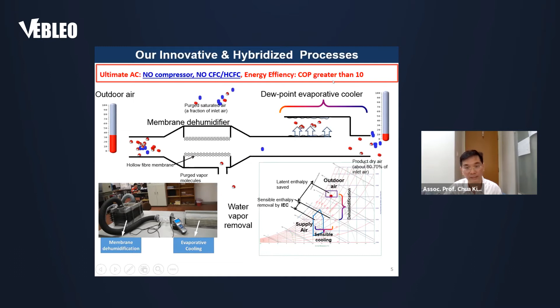So one stage of this system, the dry and wet channel, will be able to drop the temperature of the air by about 3 to 4 degrees. So if you desire maybe about 10 degrees of temperature drop from your air, then you need to repeat this process 3 times. In other words, the air that is coming out from this entire system is both cool and dry, similar to what you get in your typical vapor compression air conditioning system. And with no compressors, no chemical refrigerant, we can reach very high COP, about 8 to 10. And that's very highly desirable. It's about 2-fold more energy efficient compared to your current vapor compression system.